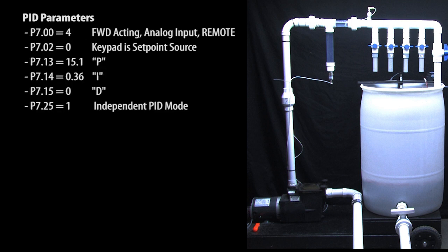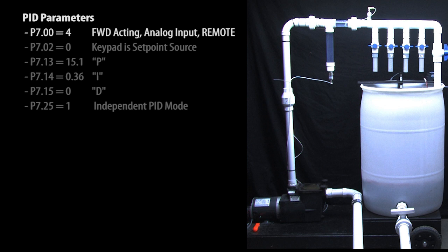These are the PID parameters we're using. This is where we tell the drive this is a forward acting system using an analog input and that for this demo will only enable PID in remote mode. The keypad is the default set point source, I'm just showing it here as a reminder.